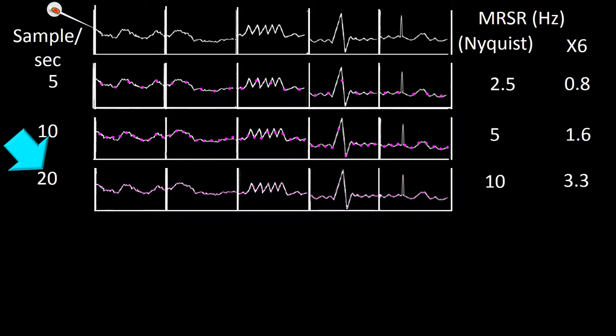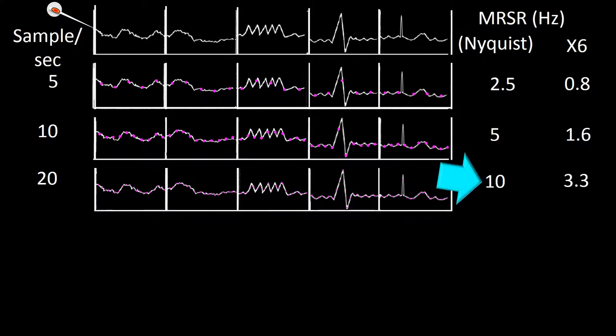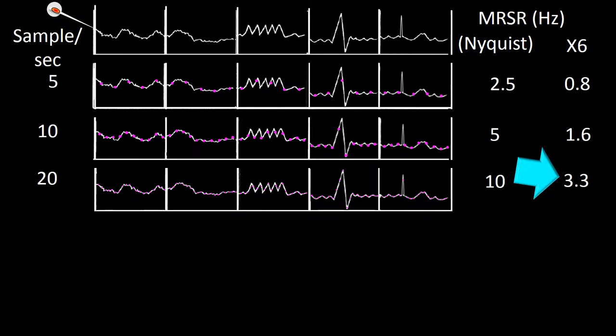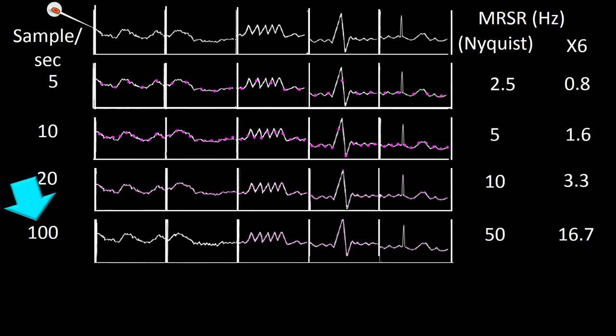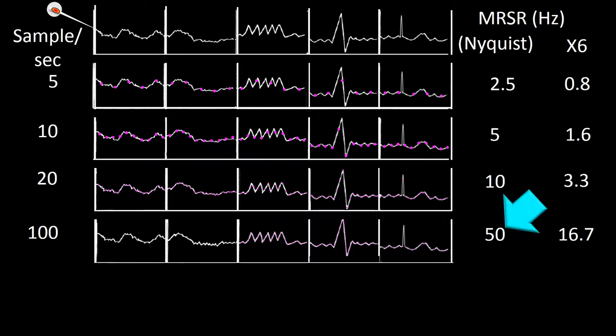Using a sampling rate of 20 per second, we could reconstruct waves of 100 ms or longer using Nyquist, but only waves of 303 ms or slower using the times-6 rule. Using a sampling rate of 100 per second, according to Nyquist we could reconstruct a wave of 50 Hz or slower, but the times-6 rule allows only waves lasting 60 ms or longer.